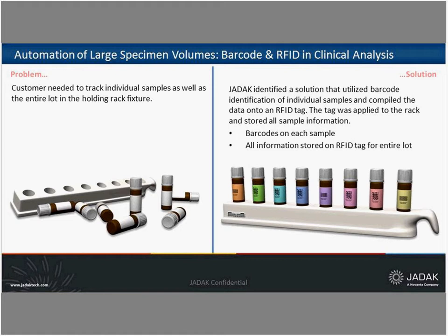Once the racks were in the device, they were robotically transported to several analysis stations where sample vials could undergo separate tests unique to each vial. So really expanding the capabilities here. At the various stations, these unique actions and tests that were conducted on the individual samples within the racks could then be updated to the tag. And the unique processes of, in this case, eight samples could be tracked via RFID data that was actually on the rack.